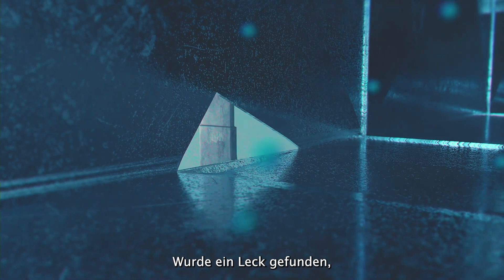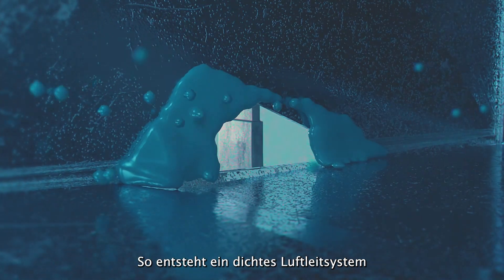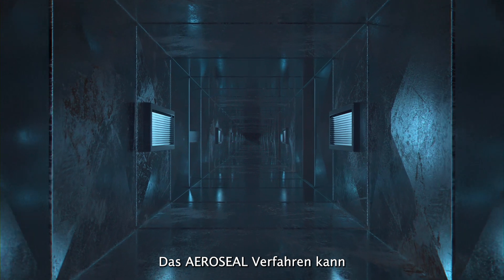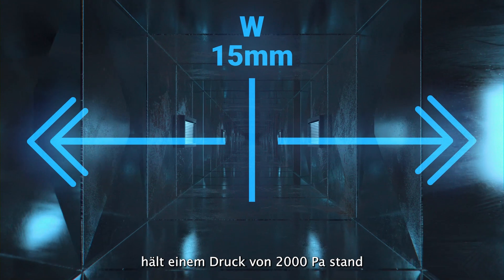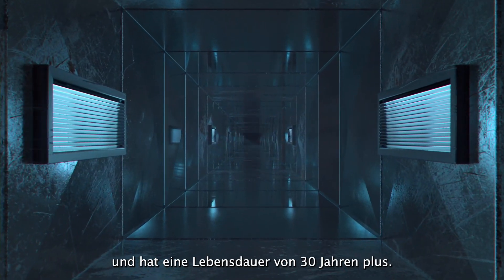When a leak is found, a layer of sealant sticks to it and seals it, creating an airtight duct system and eliminating the need for expensive building modifications. The AeroSeal sealant is capable of sealing leaks of any type up to a maximum of 15mm wide, is able to withstand 2,000 Pa of pressure, and has an estimated lifetime of 30 years.